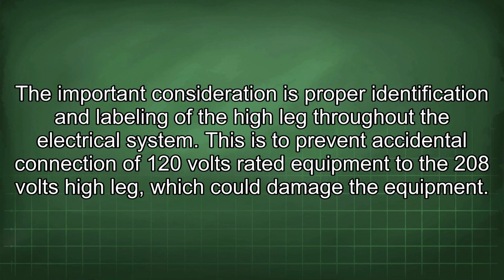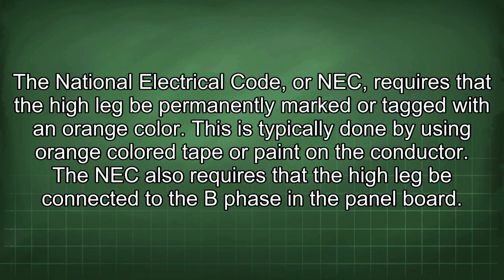This is to prevent accidental connection of 120 volt rated equipment to the 208 volt high leg, which could damage the equipment. The National Electrical Code, or NEC, requires that the high leg be permanently marked or tagged with an orange color. This is typically done by using orange-colored tape or paint on the conductor.